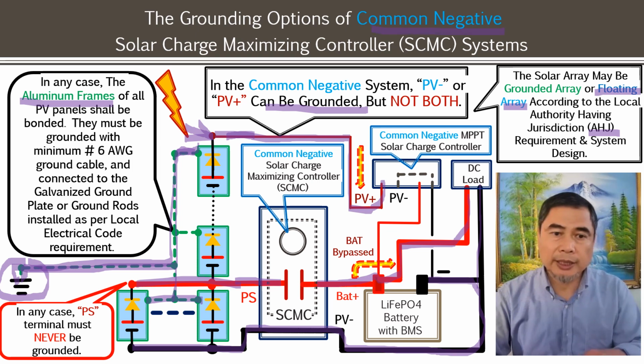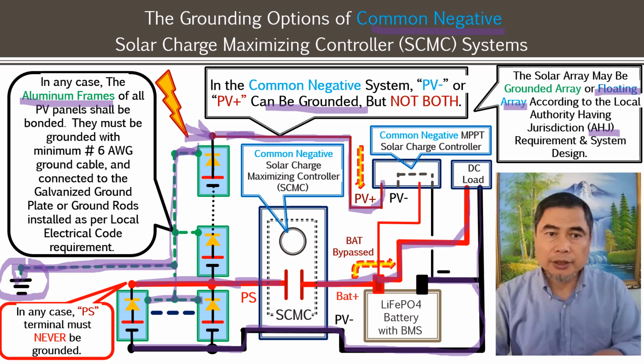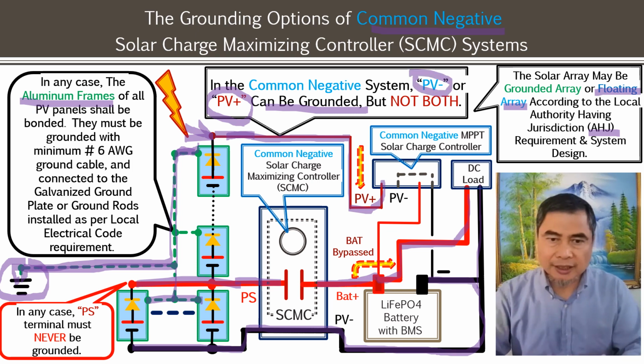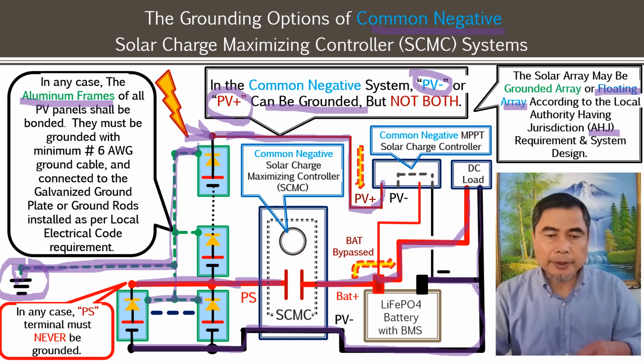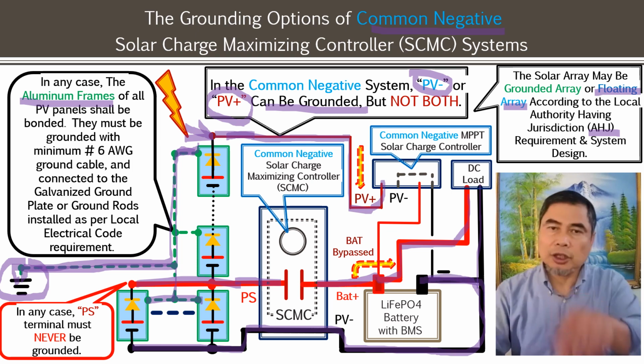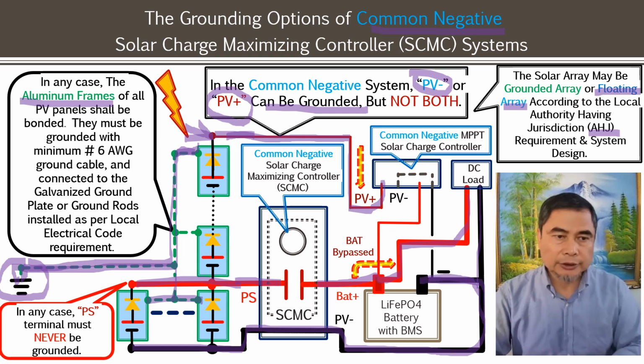So this is a common negative design. The way it's set up, you see that it's a common negative. You have an option: you want the PV positive to be grounded, or you want the PV negative to be grounded. It's based on your design. Just remember that if it's a common negative system, grounding PV negative means battery negative is also grounded. So that's just something you want to know.